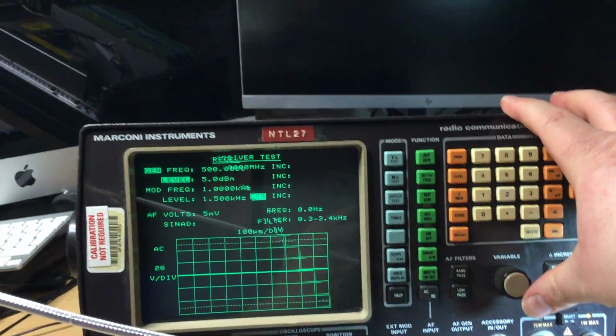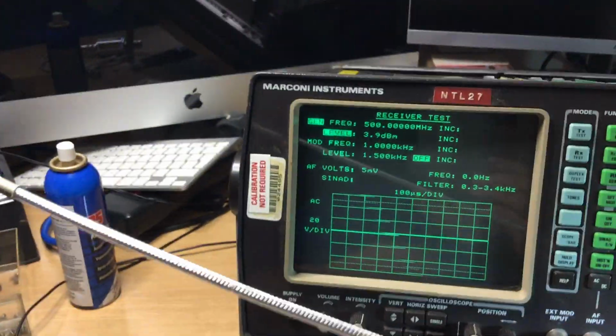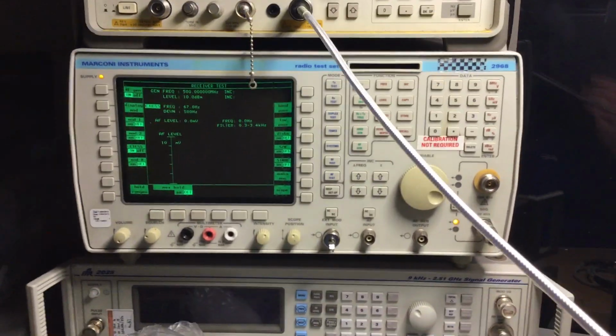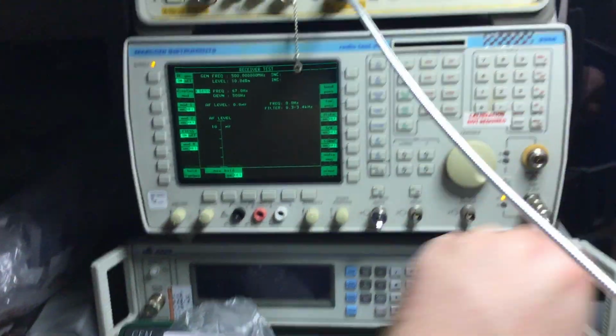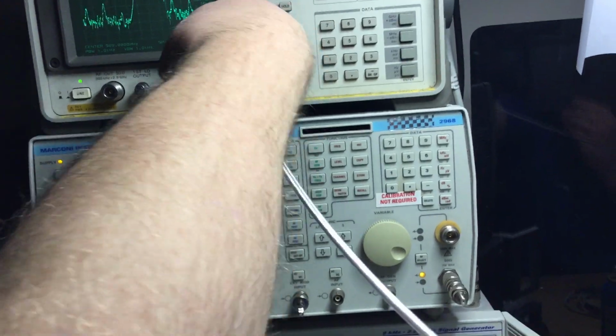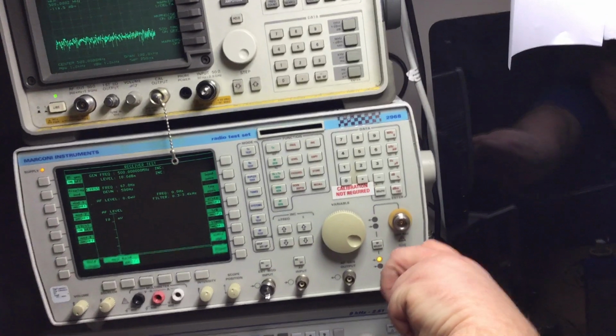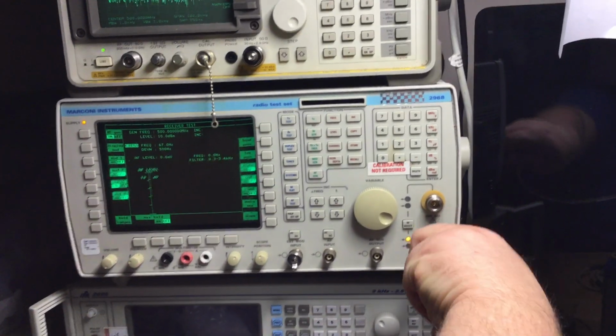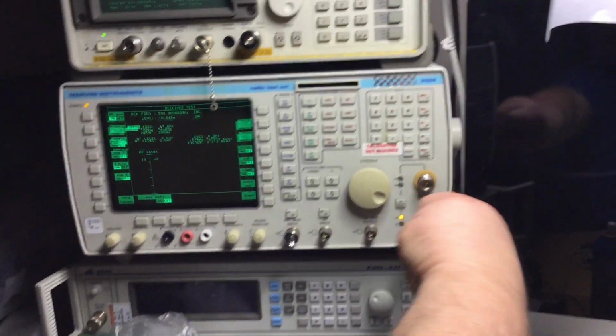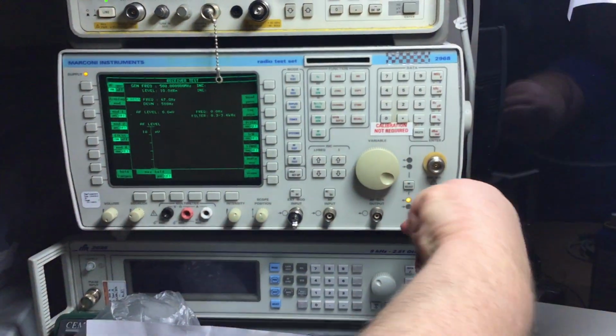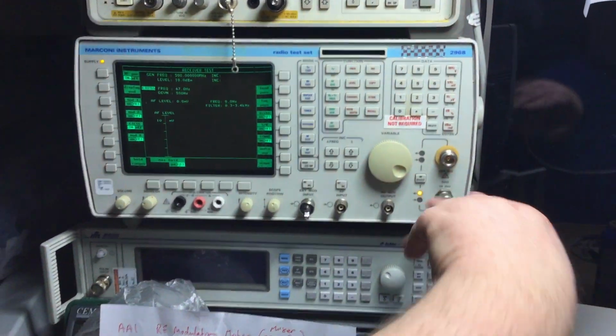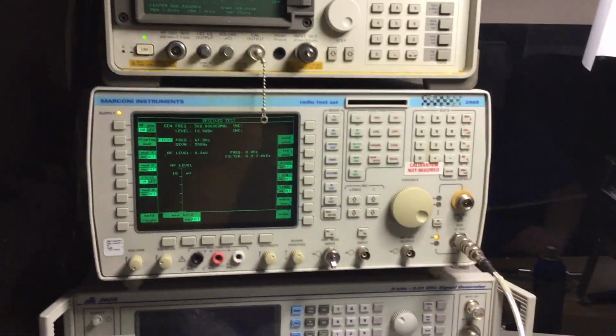We're going to inject a signal now into the 2968 test set, and we're going to do that so that we can check the modulation output on the Marconi 2955. Again, if you've got separates, you could do the same thing with a mod meter, deviation meter. You know, if you've got one of those little Racal-Dana things, you don't have to have expensive or fancy test kit to do these tests yourself.